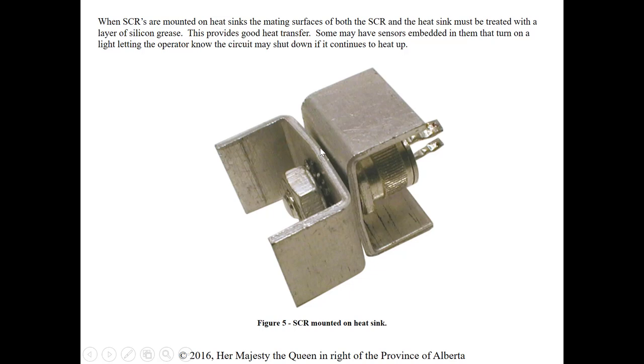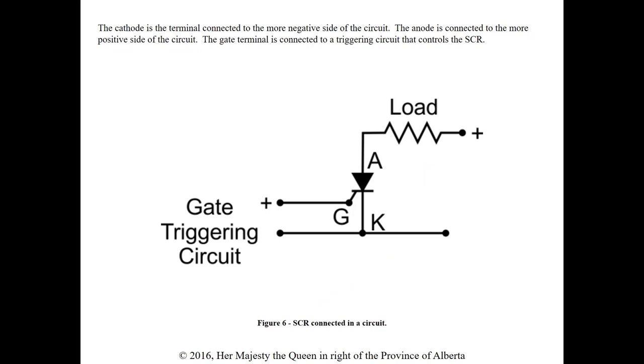Heat sinks must be used to dissipate heat, and they need layers of thermal grease so that we have good heat transfer without air pockets. Some SCRs even have sensors embedded in them to turn on a light letting the operator know that the circuit may shut down if it continues to heat up. Dissipating heat away from these components is critical — heat going to electrical components can potentially destroy them.